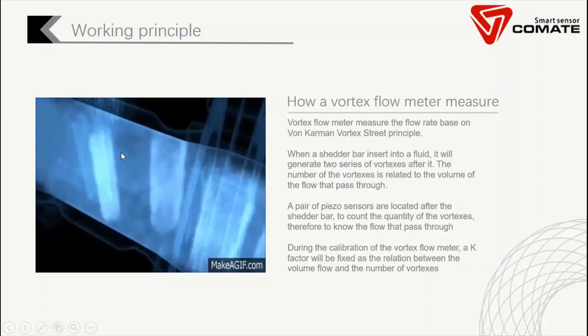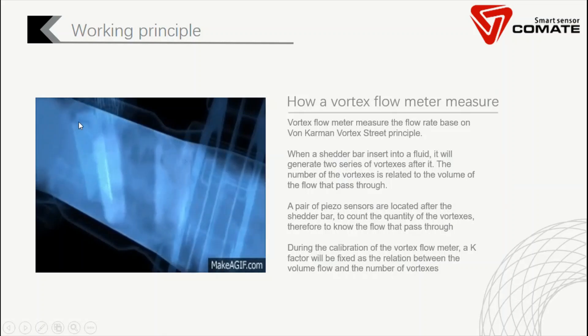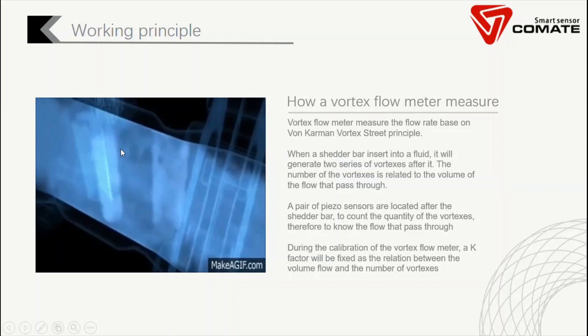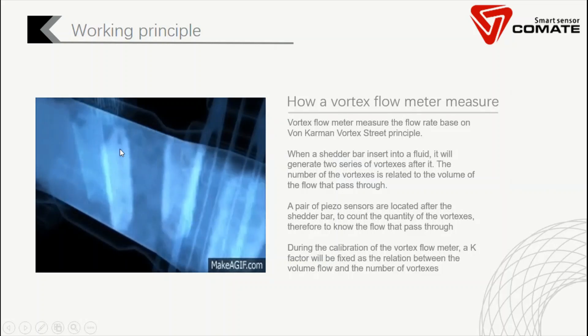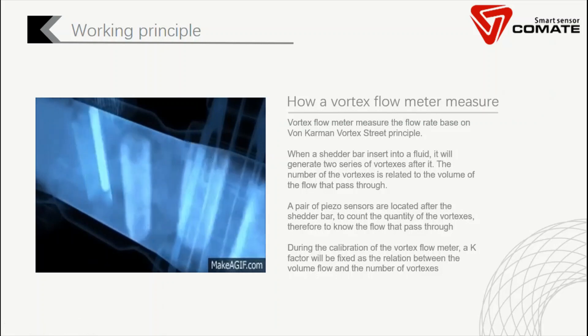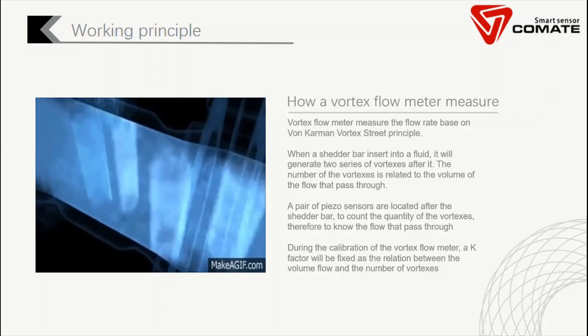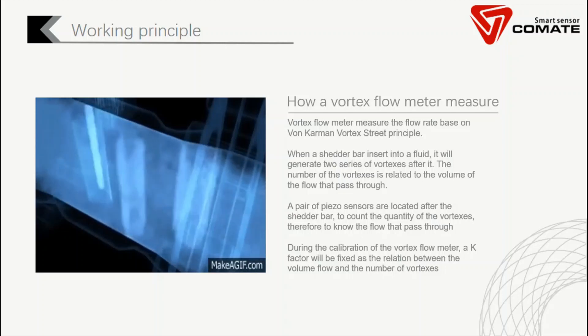In a vortex flow meter, we have a shedder bar here. We also have a pair of piezo sensors after the shedder bar, which can detect the micro pressure change caused by the vortexes. So we can count how many vortexes have passed through, and therefore we can know the flow rate.